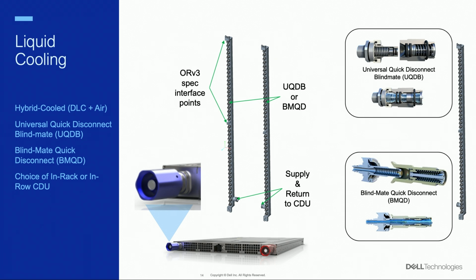Moving forward, we complete the liquid cooling solution with manifolds and blind mate connections, because the Open Rack V3 specification also defines the shape and the position of those connectors. On the market, there are basically two standards. The one you see on the top is the universal quick disconnect blind mate, which allows only for vertical tolerance. The one you see on the bottom is the blind mate quick disconnect, which is a slightly improved version with an additional O-ring in the connector, which allows even radial tolerance, so it can be easier to deploy servers with those connectors.